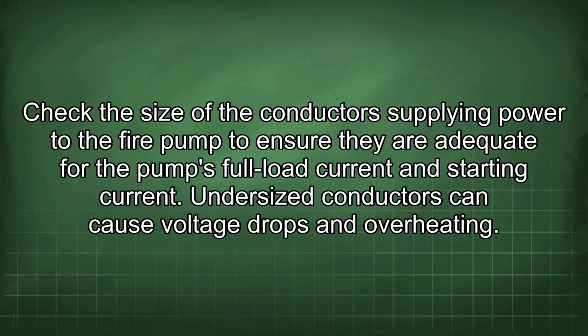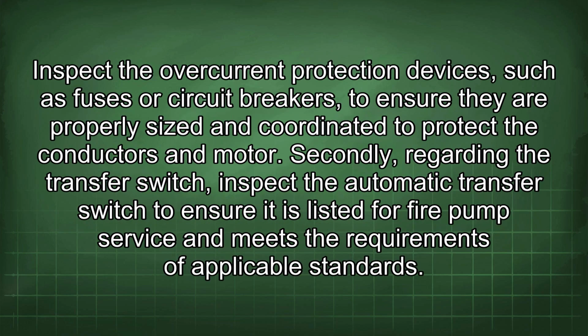Check the size of the conductors supplying power to the fire pump to ensure they are adequate for the pump's full load current and starting current. Undersized conductors can cause voltage drops and overheating. Inspect the overcurrent protection devices, such as fuses or circuit breakers, to ensure they are properly sized and coordinated to protect the conductors and motor.